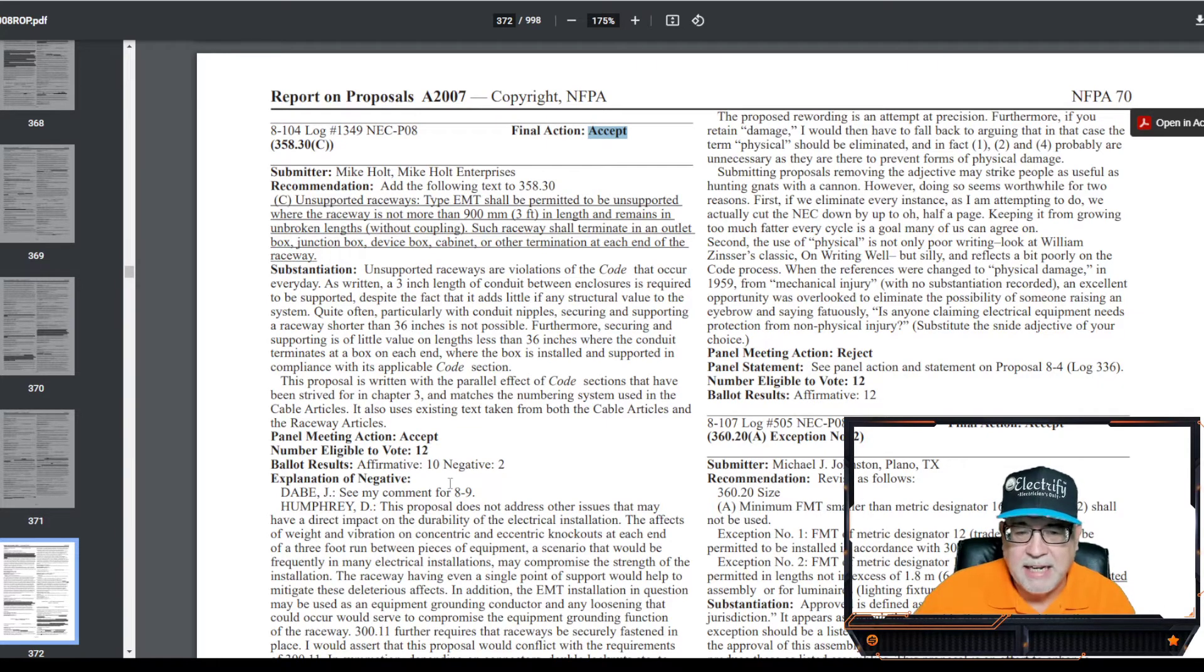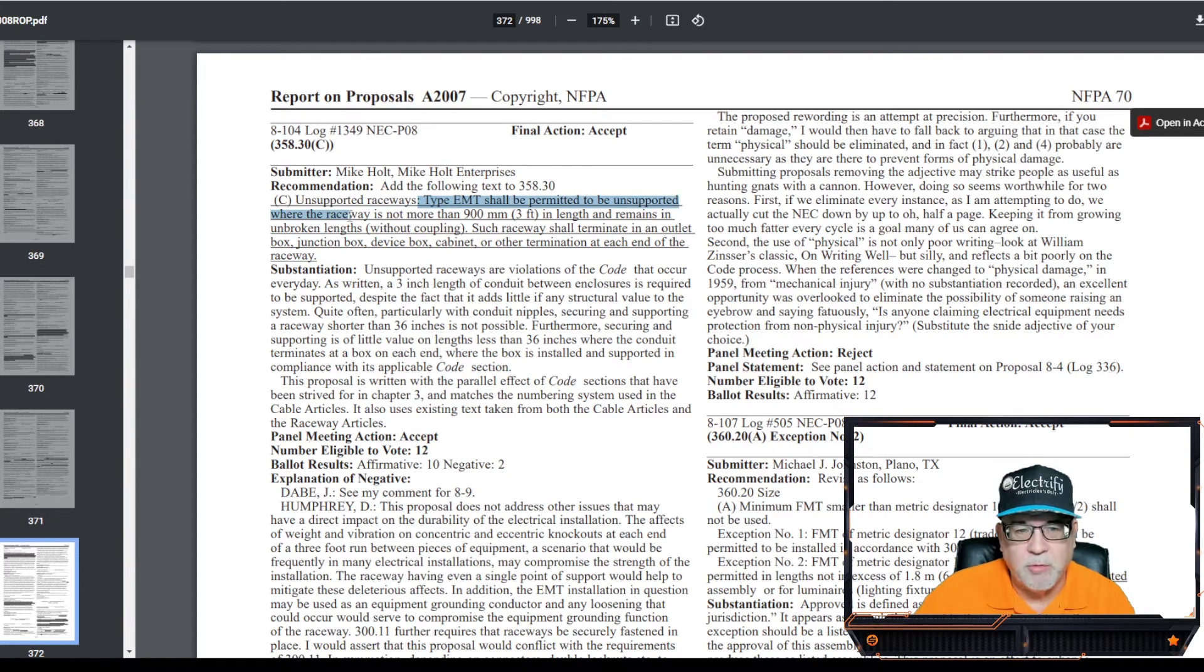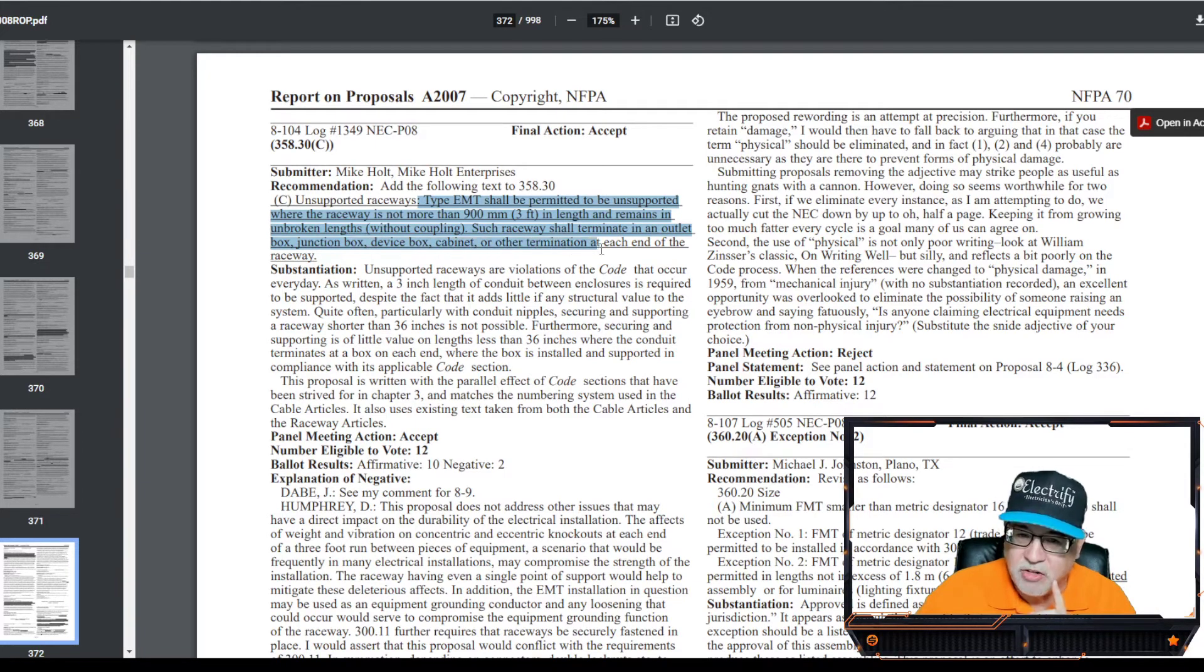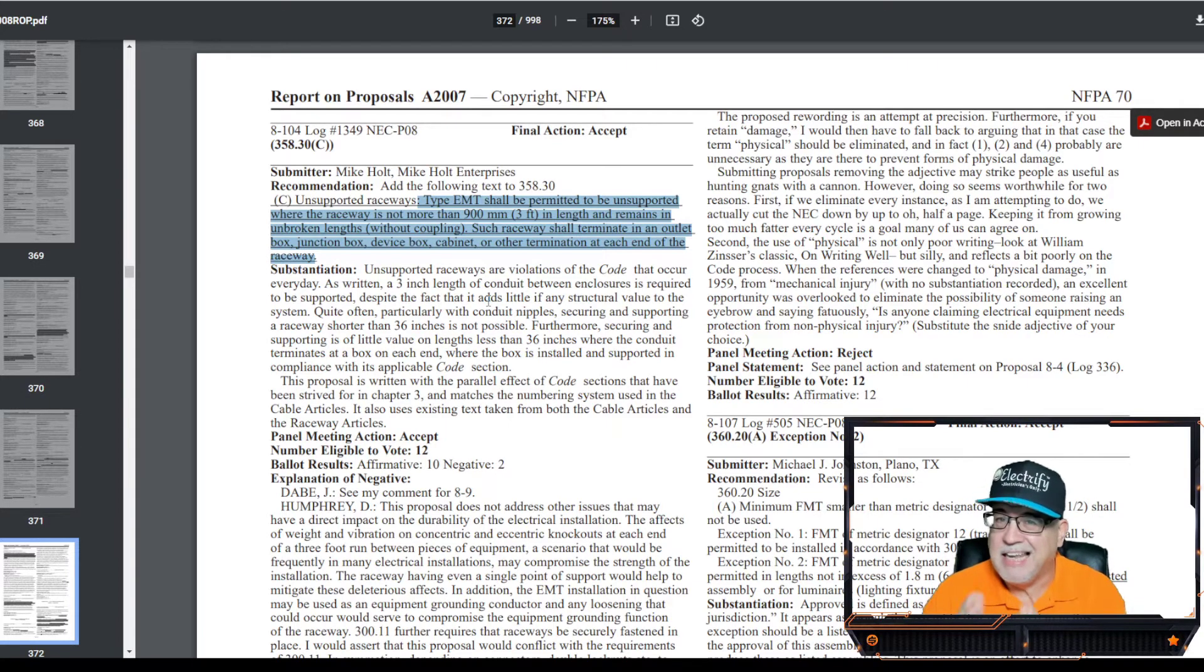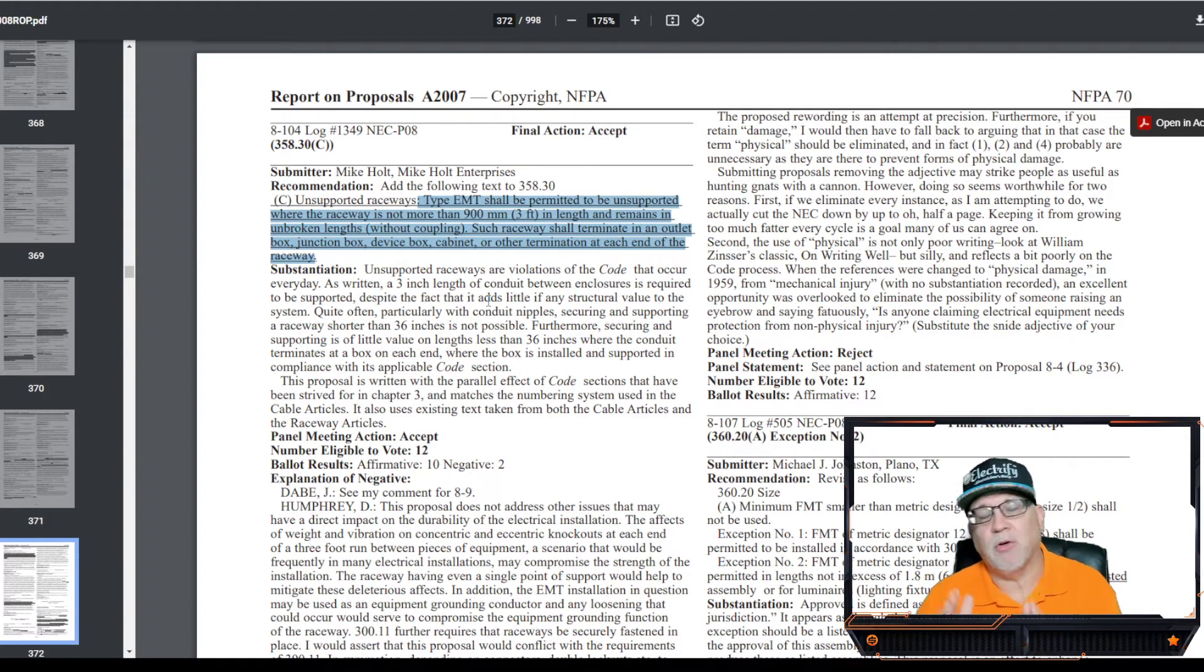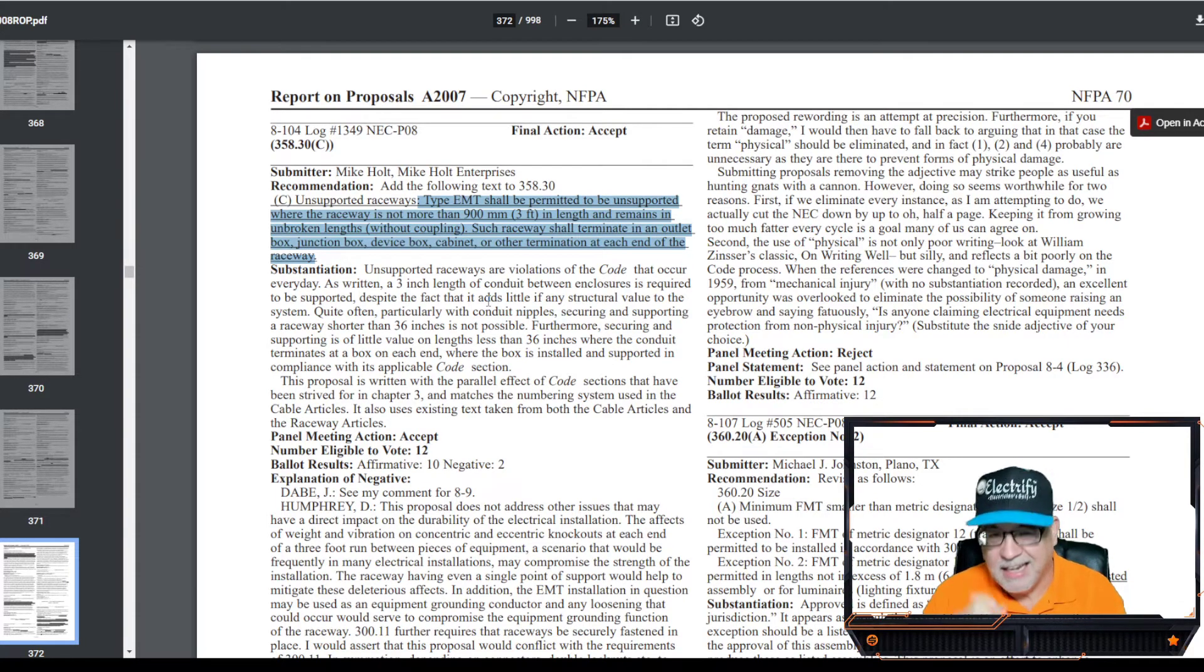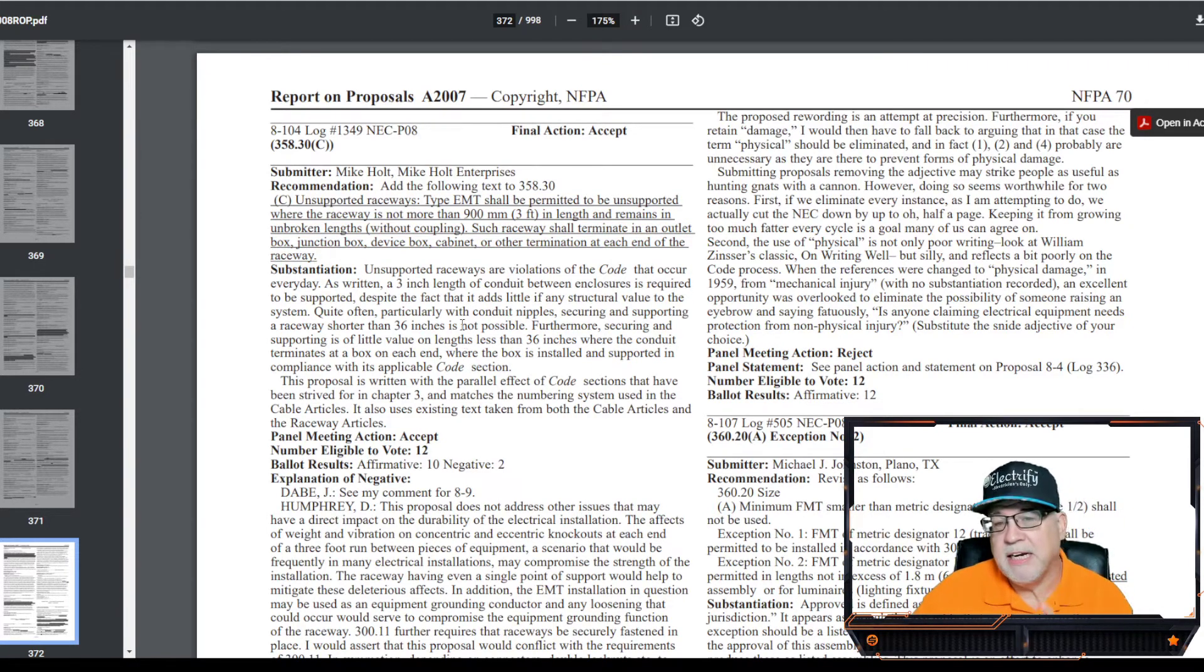It says add the following text to 358.30. So this is 8-104, the log. This is to code panel 8. It was accepted by code panel 8. And the rationale, it wasn't unanimous. It was 10 to 2. But here's what they said. Unsupported raceways. Type EMTs shall be permitted to be unsupported where the raceway is not more than three feet in length and remains an unbroken length without couplings. Such raceways shall terminate in an outlet box, junction box, device box, cabinet, or other termination at the end of the raceway. So the tubing, when it ends, it ends at a coupling. It ends at a cabinet. It ends at a junction box. It's when that joint or that stick or modified stick that you happen to cut off at certain length ends, and it ends in a fitting.